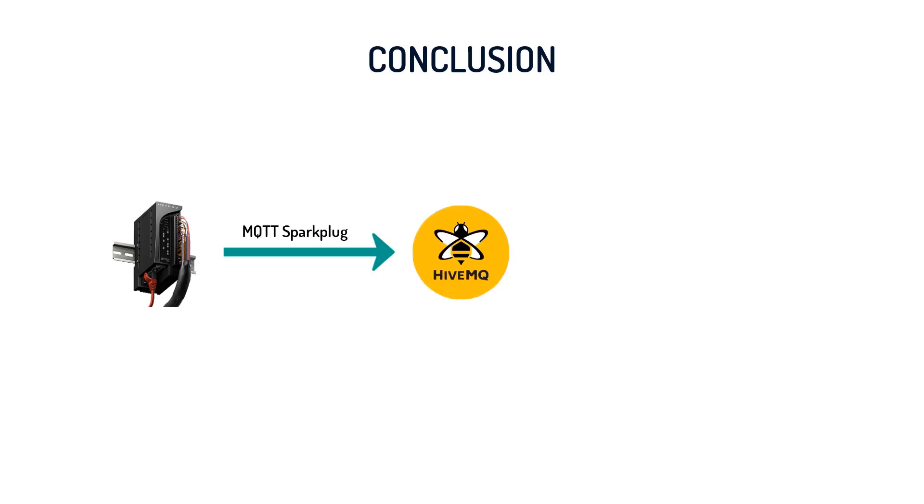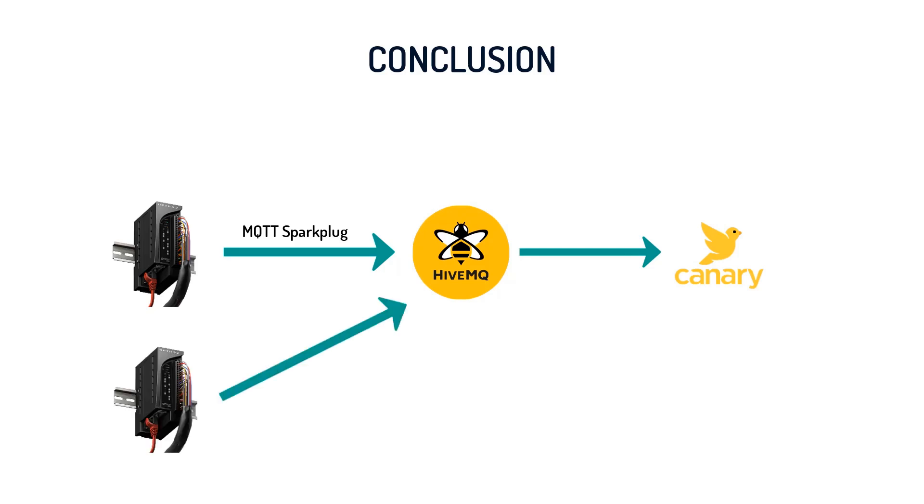So we've managed to collect process data from a plant floor device, send the data as MQTT Sparkplug B messages to HiveMQ cloud, and forward it to Canary Cloud historian for visualization without writing any piece of code. Now, if I start publishing from another Opto 22 or any other Sparkplug B enabled device into the same HiveMQ cloud broker, the Canary historian would automatically discover the data and add it to graphs.